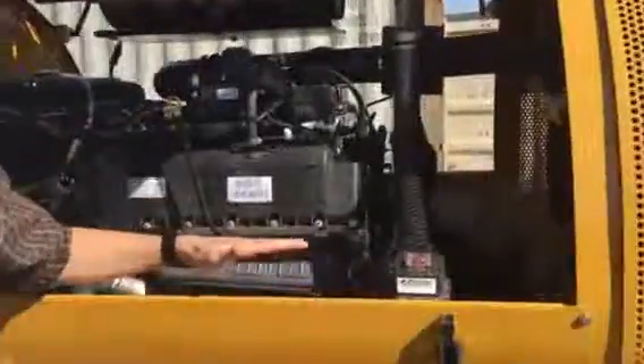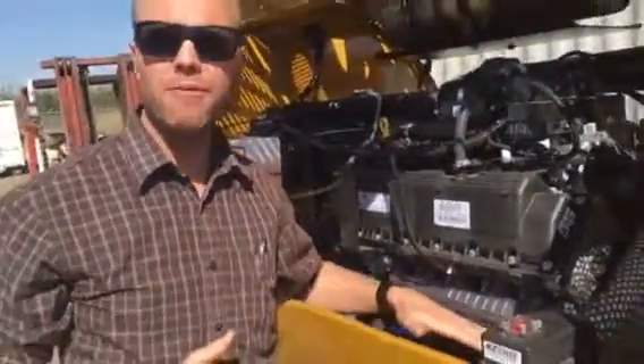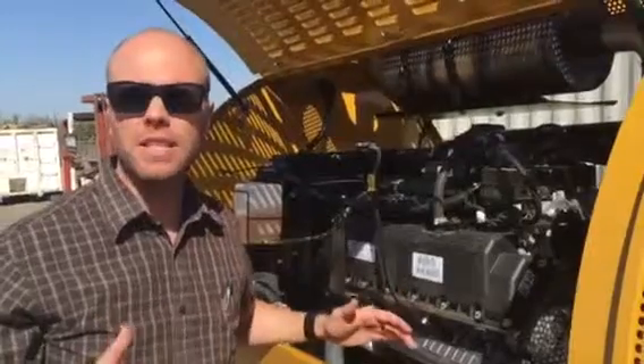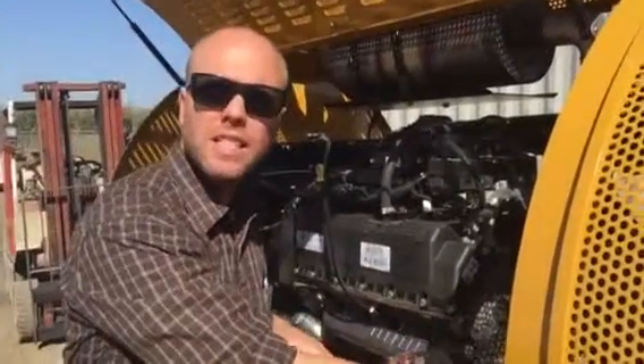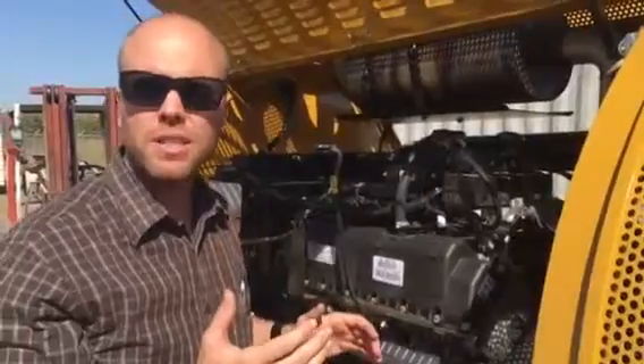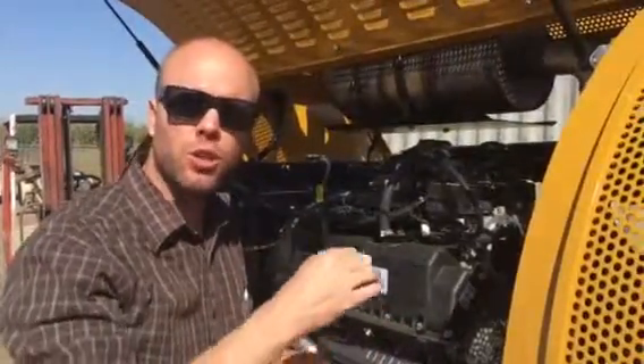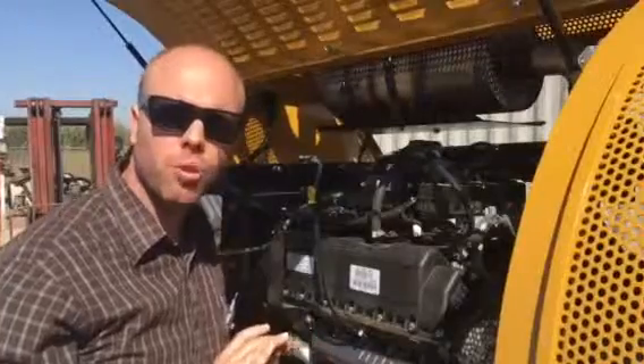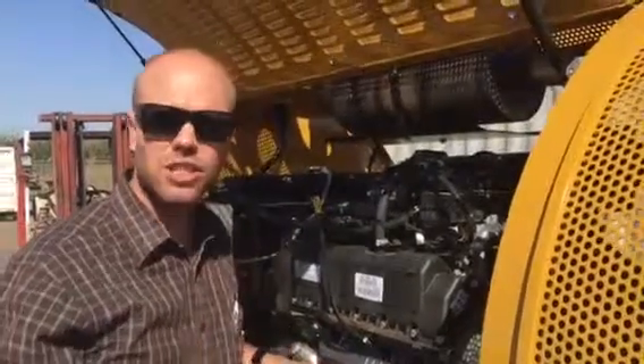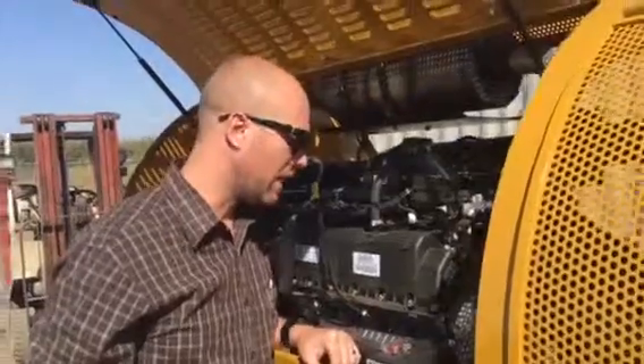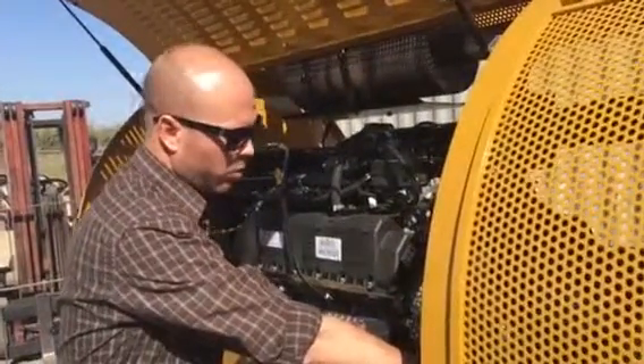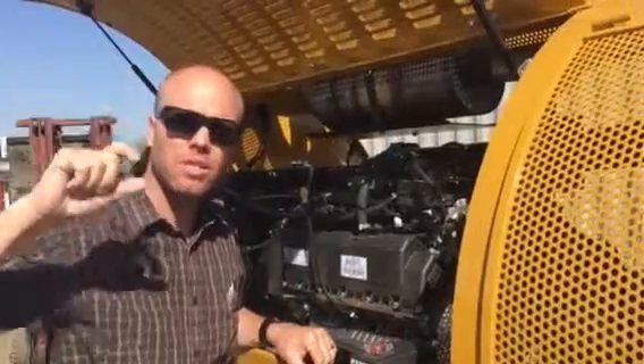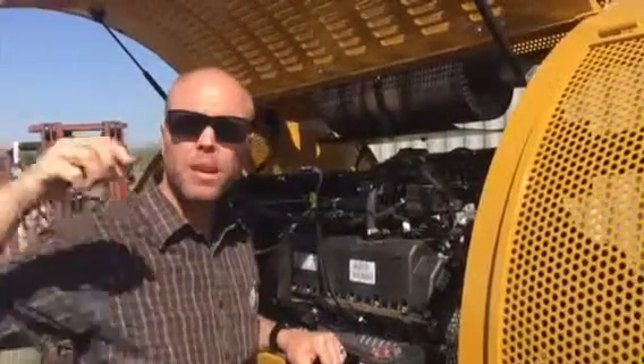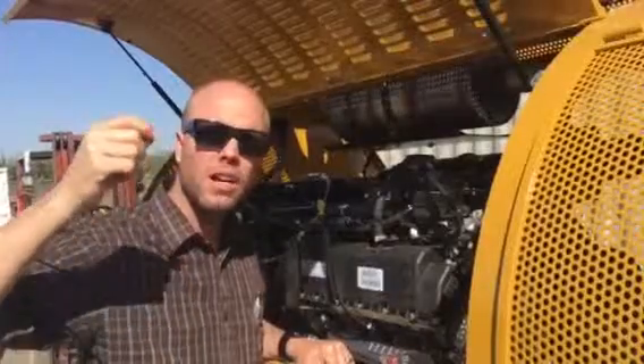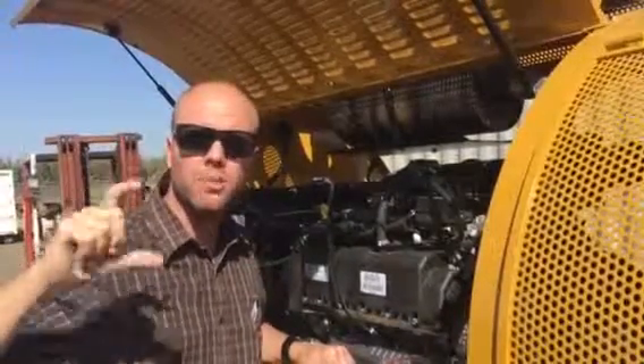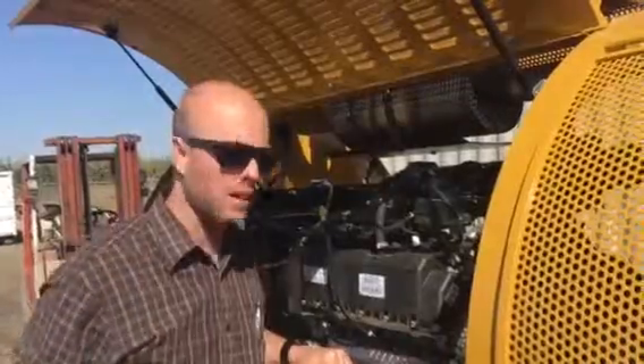Maintenance on the pump. So this pump is a very robust pump. Typical service life is 10 to 15 years if it's maintained properly. There's a couple of grease points that need to be addressed on a 40-hour type basis. You want to grease them to a certain fill level. You don't want to over grease because you can actually force the seal out of the pump, and that just lends for debris to get into the bearings. We supply this with a 9/16. It's actually not a 9/16. It's a quarter pipe plug, but it takes a 9/16 end wrench to pull the plug, and we typically use a piece of welding wire or something. You want about 2 inches of grease in that cavity.